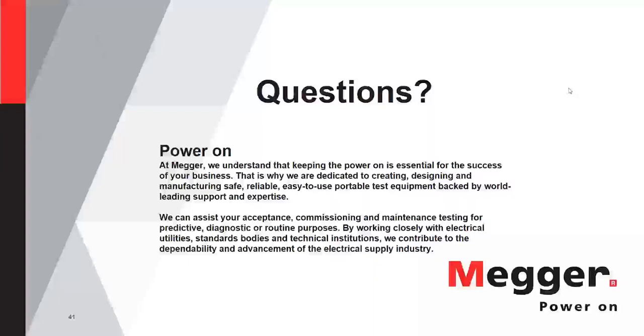So when you look at your percentage of change from baseline, like I said, with a flooded lead acid, 50 to 100% is good, but when you get to a VRLA, you might want to be a little bit more cautious if it's in a critical application and say 20 to 30%. So I hope that answers that somewhat.